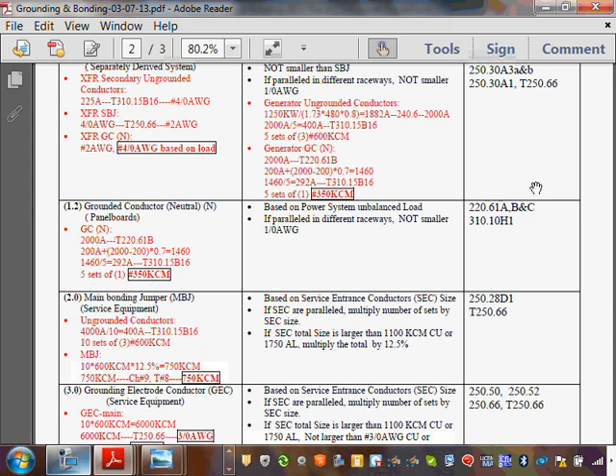This is how I size a neutral. The code says, guys, based on the unbalanced load, but you go to a service and you have no idea how much you can. If you're at this level, you have to calculate your load. But the worst scenario that you're going to encounter is coming from 220.61(B), that I use all the time. So you assume all this load could be neutral, which is the worst scenario, and then apply the 200 amp, the amount higher than 200 amp cut by 70%. Do you guys remember that rule when you size your neutral? And then you end up with 5 sets of 350. Why 5 sets? Because I'm taking 5 sets to feed the sub panel. So that's how we size the neutral for the 1.2.